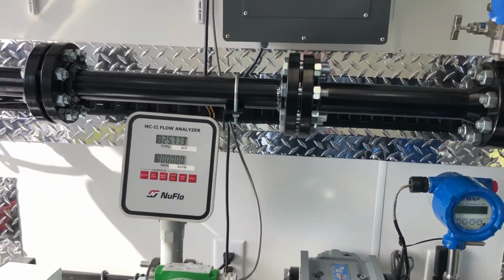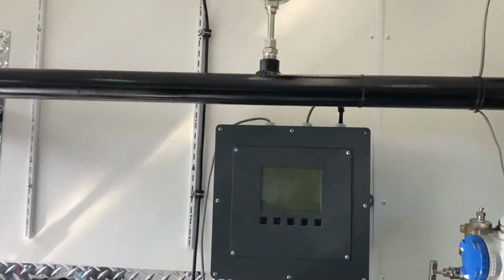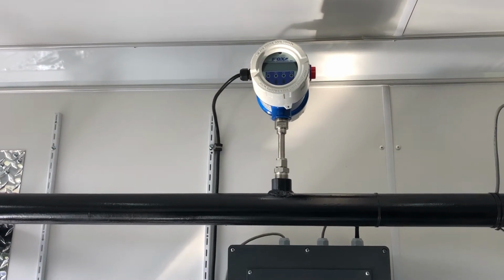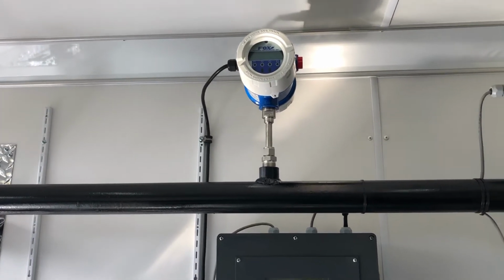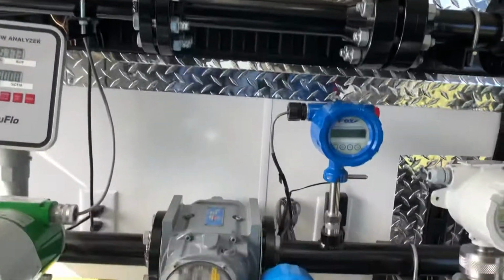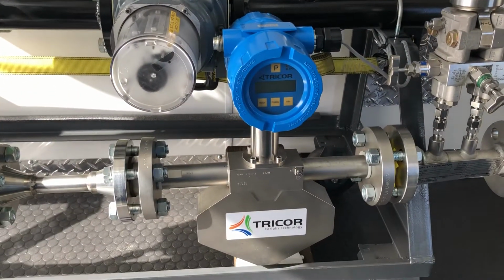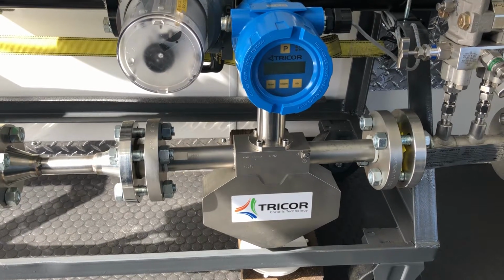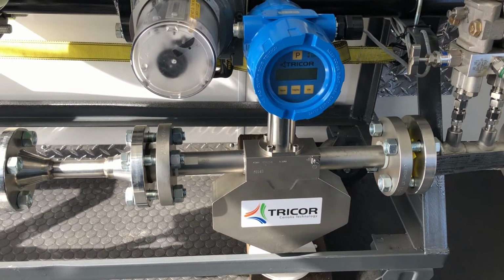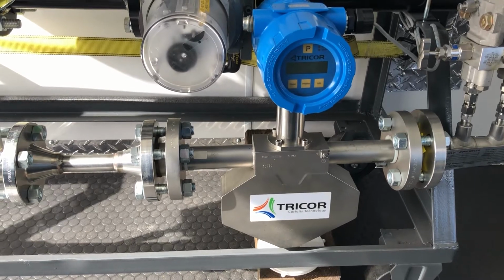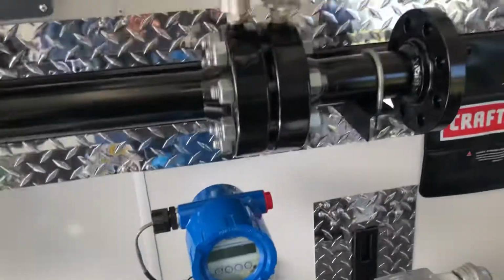And all those devices I just mentioned, you can compensate as well. But with the advent of the digital technology, there are 2 clear leaders in the industry. Thermal dispersion, which measures directly in mass units, as well as a Coriolis meter, which also measures in mass units. This uses 2 tubes that oscillate, and they measure the frequency change of the 2 tubes as the gas flows through the actual pipe.